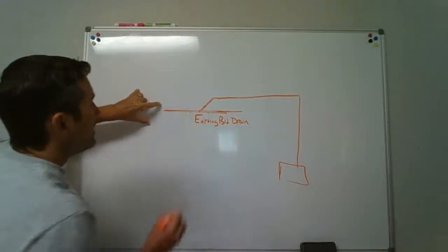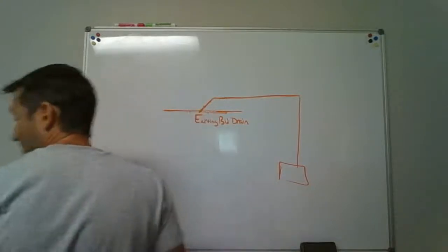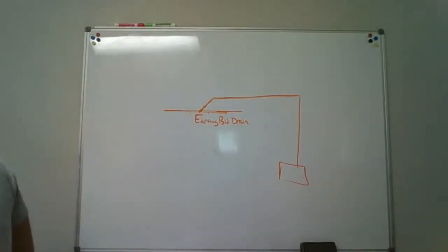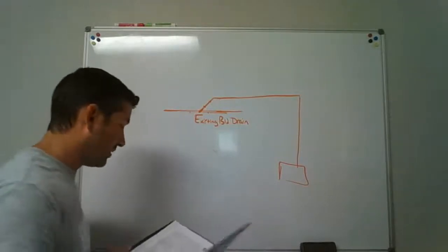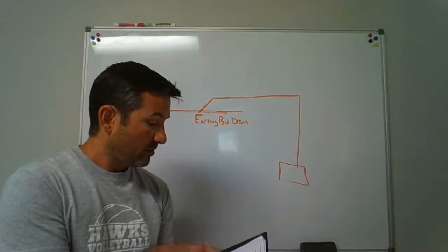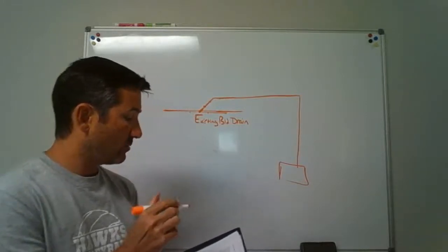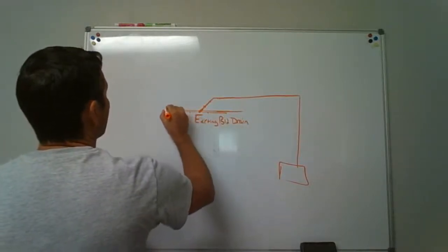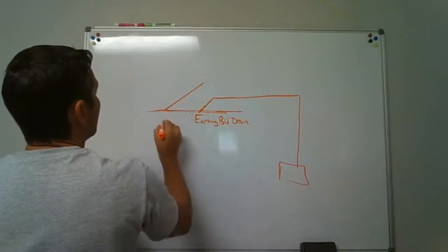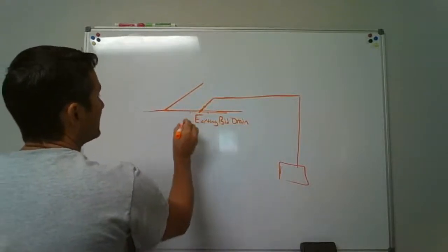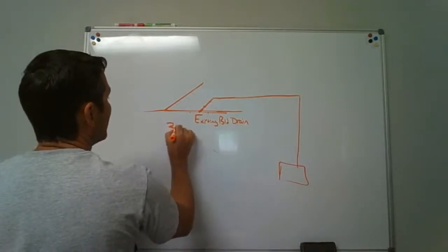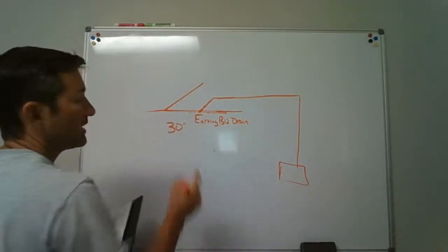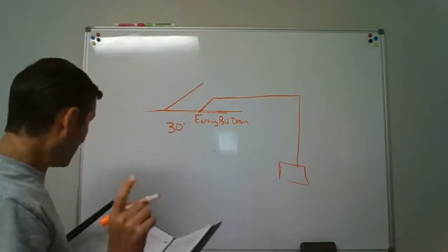It also says, though, this has to be, okay, it says what? 10 feet from the connection. Okay. We're still reading, not less than 10 pipe diameters from the base of any, so 10 times the pipe diameter. So if we came out and we had a branch or something coming into here, if it was a 3-inch, it says, well, we've got to be 10 times, so that's 30 inches away from another connection or from the base of a stack or anything.